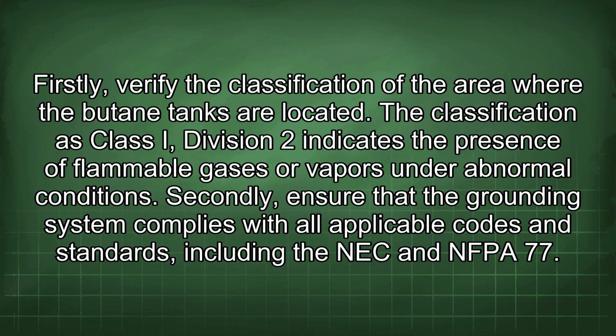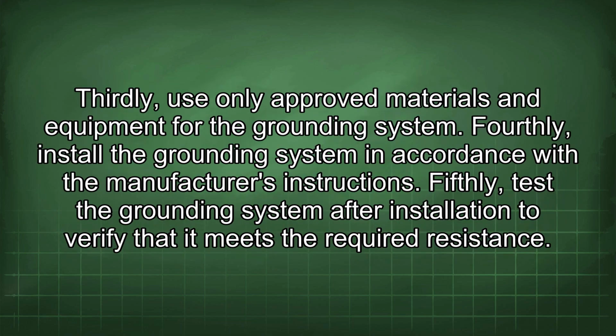Firstly, verify the classification of the area where the butane tanks are located. The classification is Class I, Division 2, which indicates the presence of flammable gases or vapors under abnormal conditions. Secondly, ensure that the grounding system complies with all applicable codes and standards, including the NEC and NFPA 77. Thirdly, use only approved materials and equipment for the grounding system. Fourthly, install the grounding system in accordance with the manufacturer's instructions.